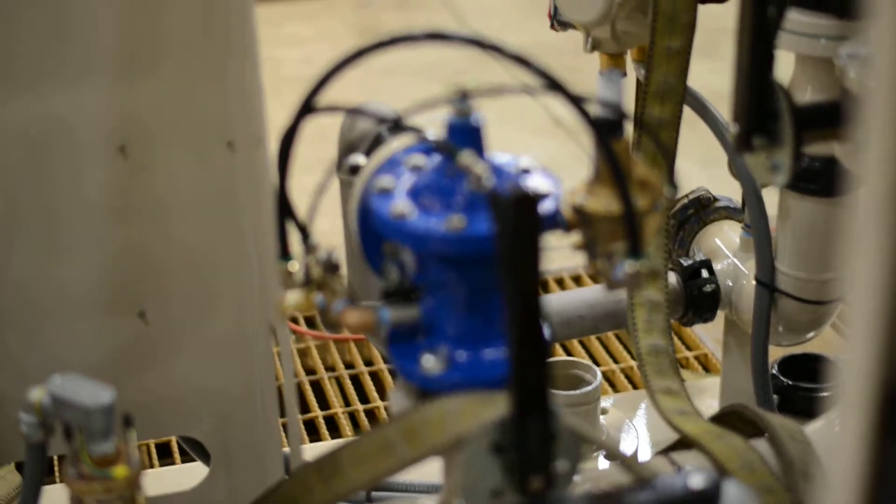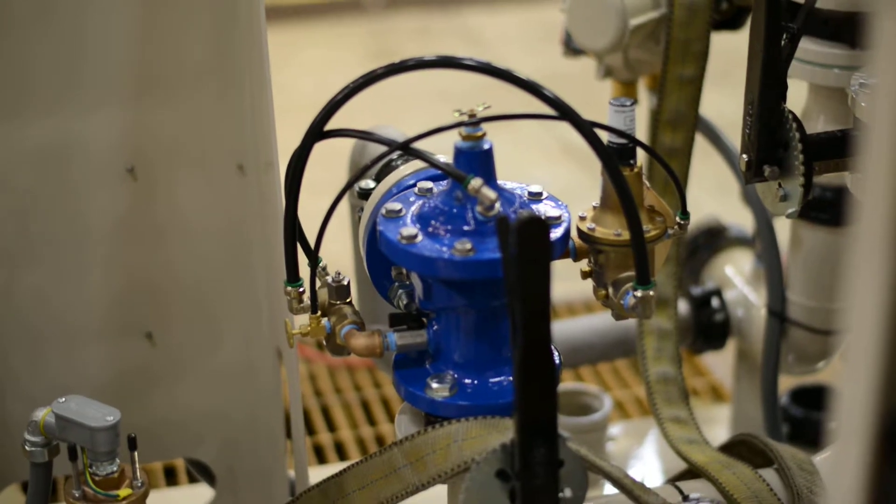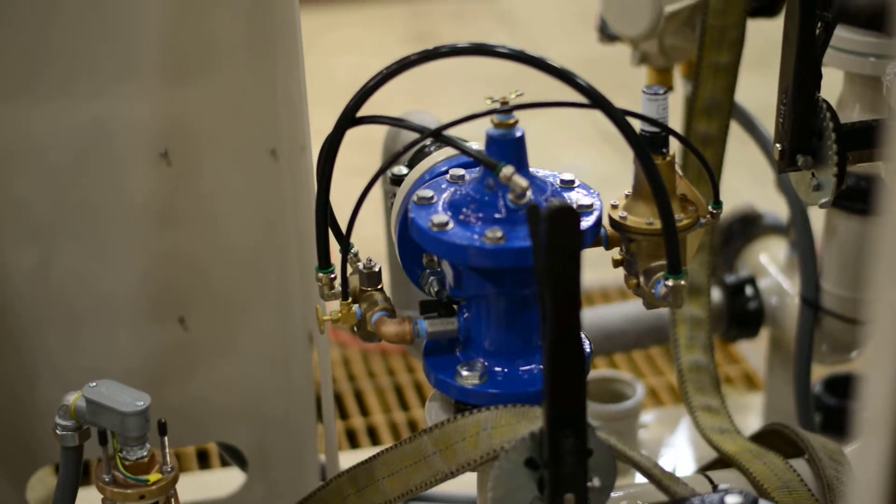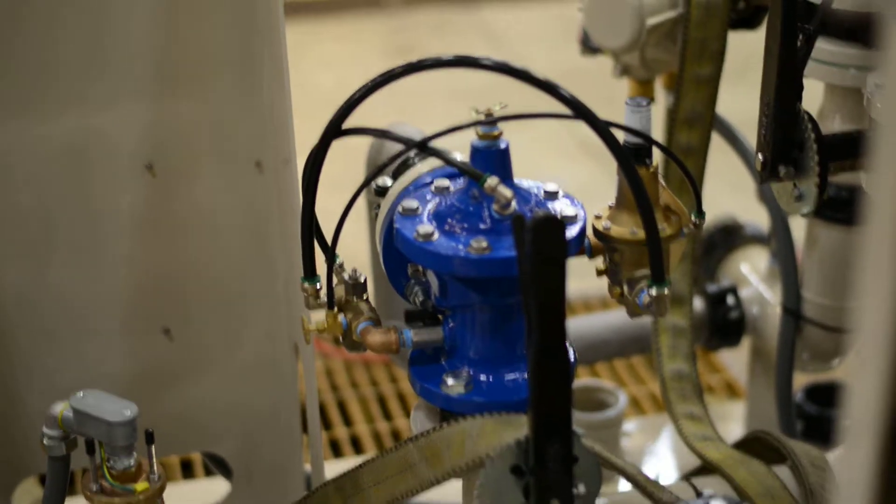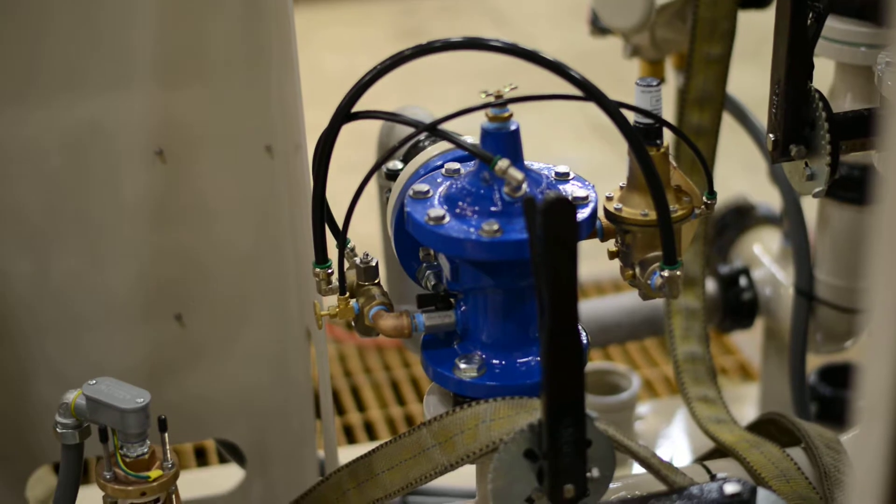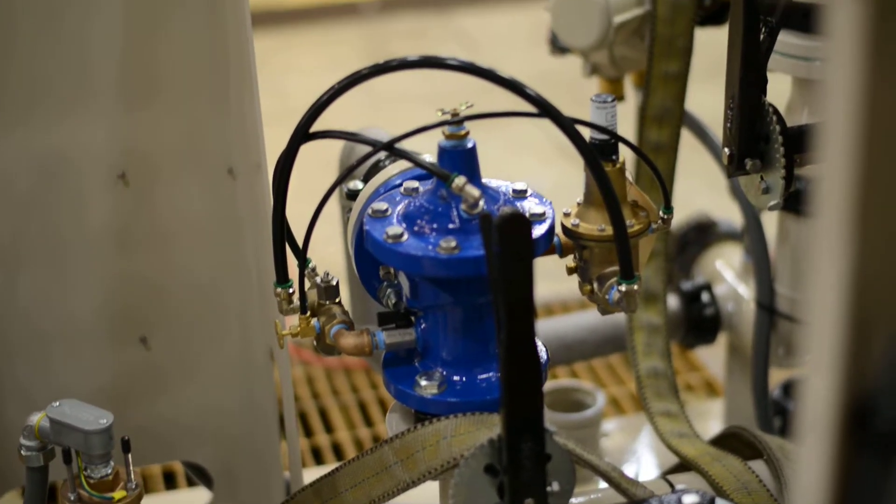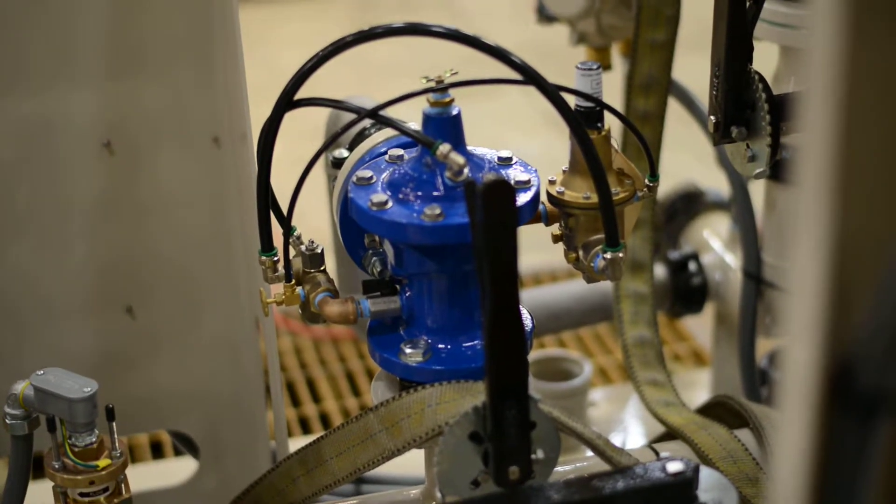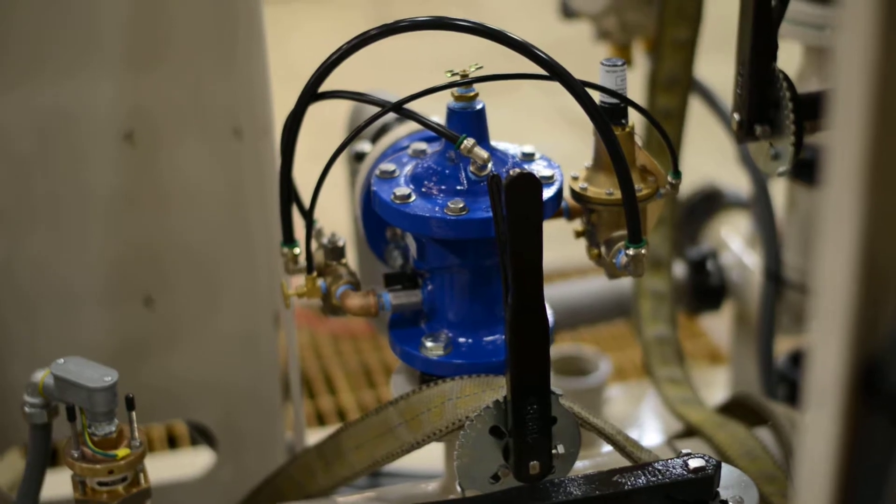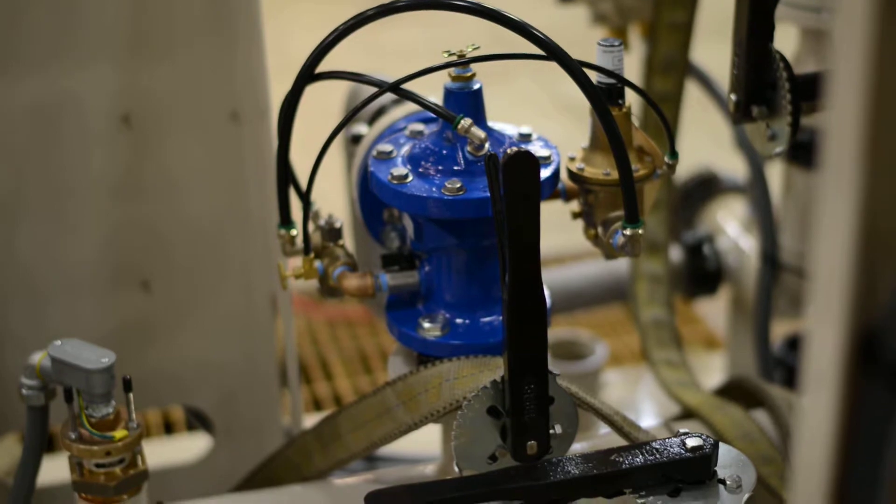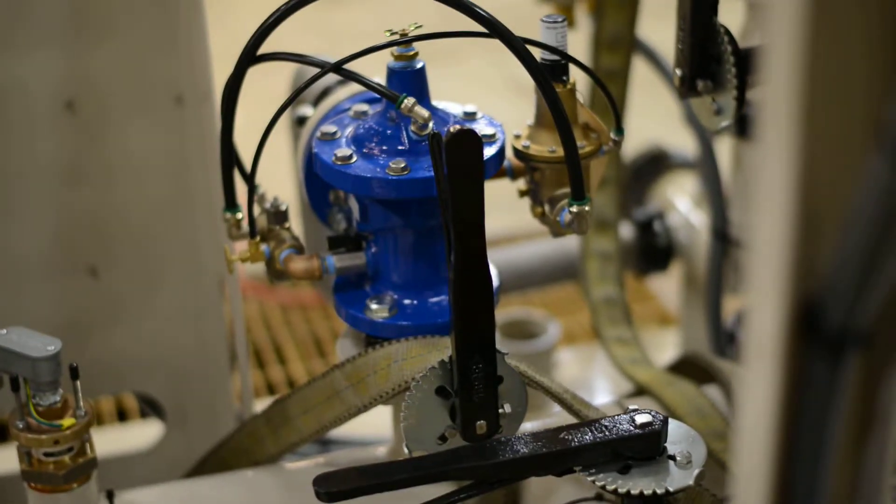What about the high pressure relief valves and all that? Have you already set all the control valves? The PRV is going to be set at 10 PSI over station set point. What we do is we'll bleed off all the air and we will adjust it so that it will open up at 10 over. We will drain it when we're done, so that valve might be closed. You just have to make sure that it's going to get opened back up so it actually functions. The PRV is set.